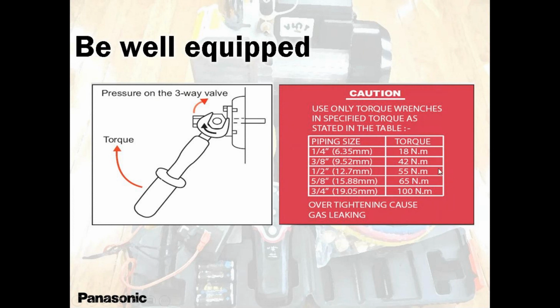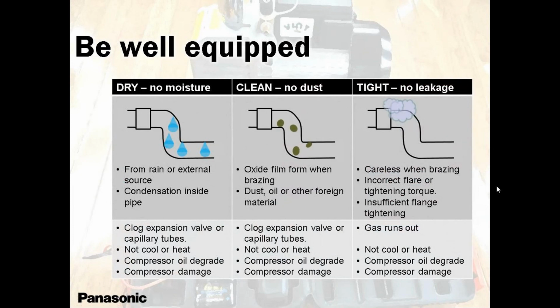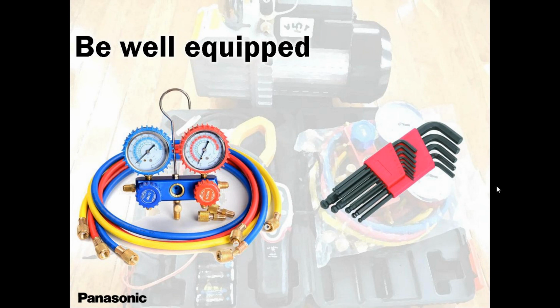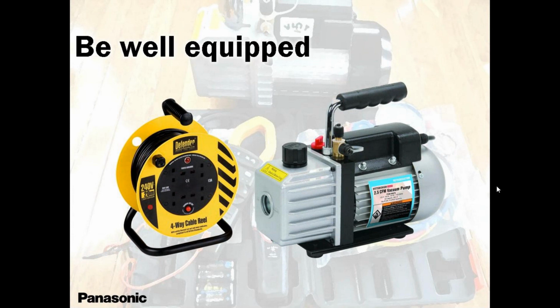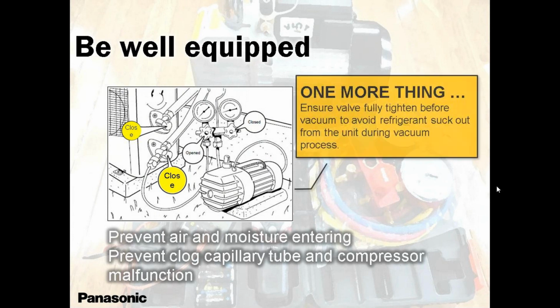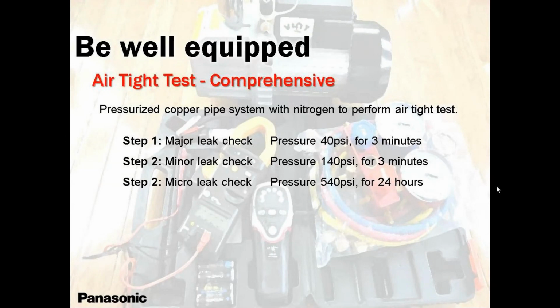I see many guys don't use, they use this. That's not good, you know. I know you are so experienced. I know, guys, you are so experienced, but try your best to use these torque wrenches. They give you the best newton-meters. Pounds per minute. Foot-pounds. You know, apply a good amount of pressure. I know it's expensive, but it can last forever if it's maintained well. And then our installation manual has all the values. For 1/4 inch, you have 18, 3/8 you have 42, 1/2 inch 55, 5/8 65. Whatever unit you use, it's easy to convert.